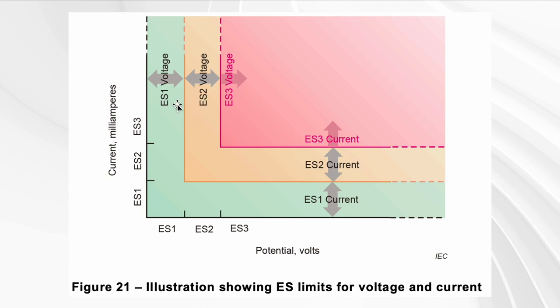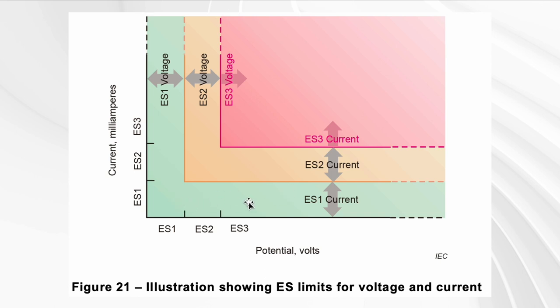The conceptual framework is: ES1, ES2, ES3. ES1 means basically safe — not going to hurt, or only very slightly. This applies when both voltage and current are very low. It's a bit more complicated than that, as we'll get to in the next slides.